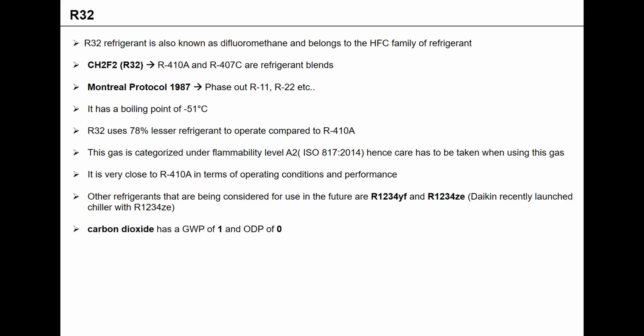The only thing is that though R1234 has a lower global warming potential compared to R32, the system size is bigger when you are developing it. So that's why Daikin said R32 is a more optimum refrigerant, with the highest efficiency for building models. The system size is also smaller. Global warming potential is 675 only, compared to R410A, which is one third less. Ozone depletion is zero.